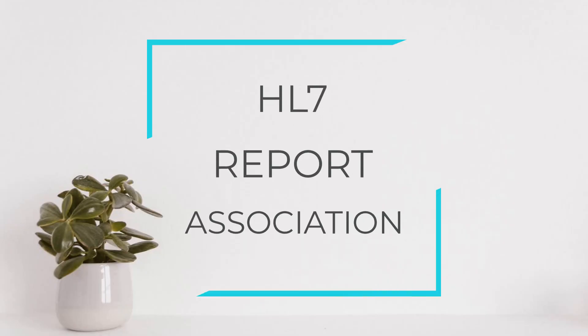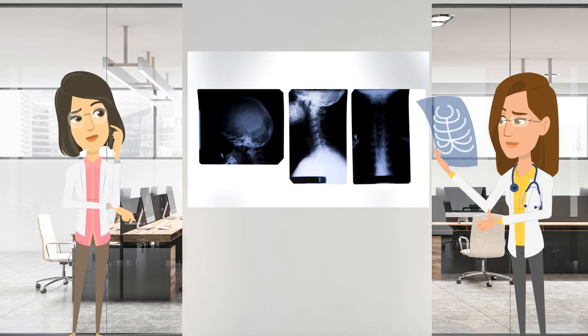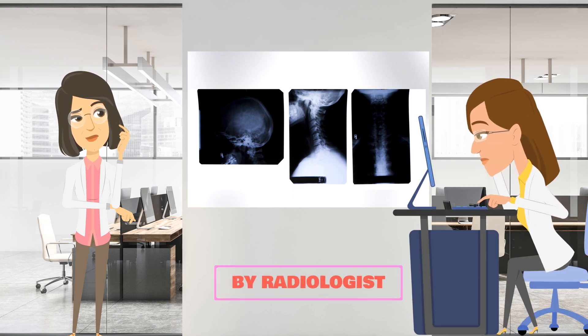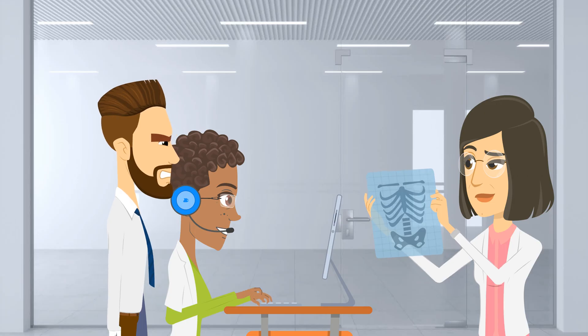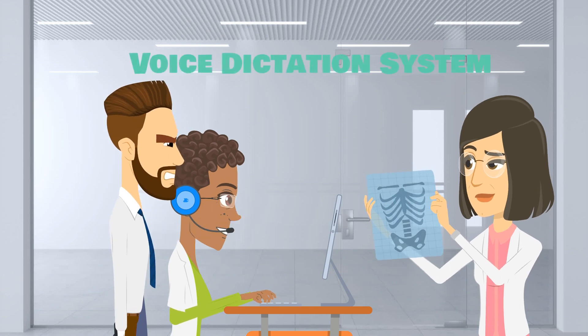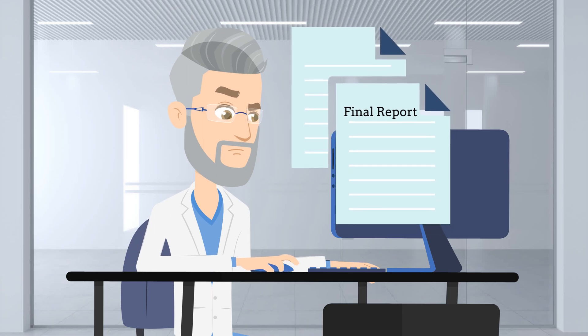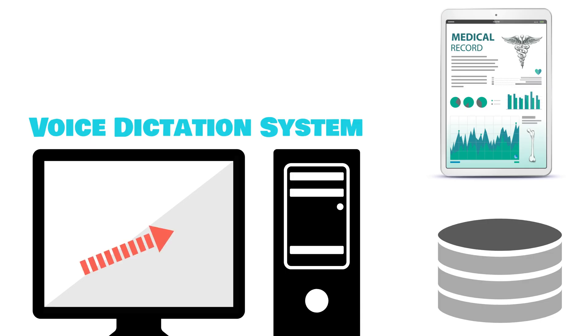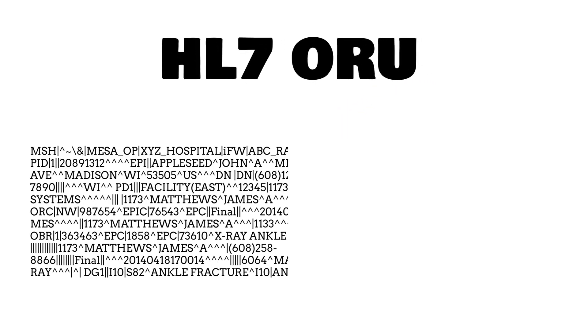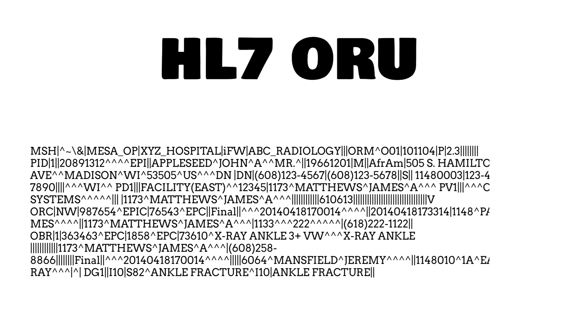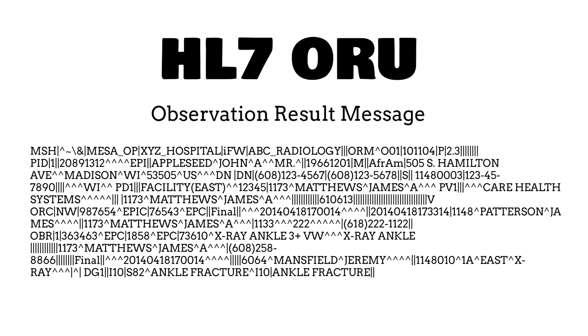Another way HL7 is used with DICOM is for report association. Upon completion of the MRI exam, the results need to be read by a radiologist. This is typically done in a separate application from the PACS — the voice dictation system. Upon completion, the textual report generated by the radiologist is sent from the voice dictation system to the patient's record and to the PACS via an HL7 message — the HL7 Observation Result Message, or ORU.